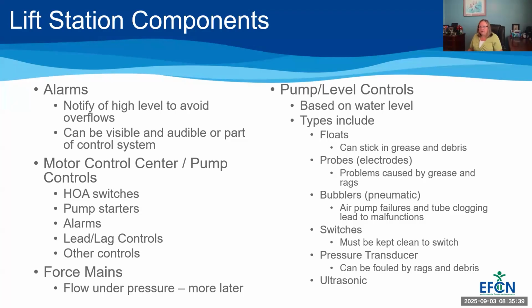Your pump starters might be in your motor control center. Your alarms might be in your motor control center. If you have lead lag pumps, meaning that you have more than one pump in the lift station and they're set to operate so that if one pump cannot keep up with the flow, a second comes on, those controls might be there in that motor control center. Any type of controls that you have are probably in your motor control center.